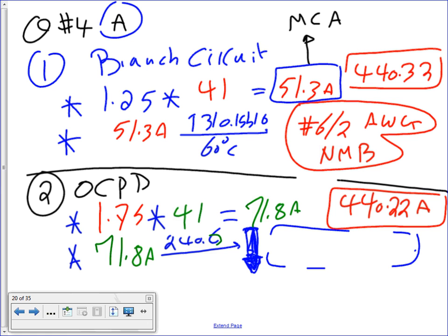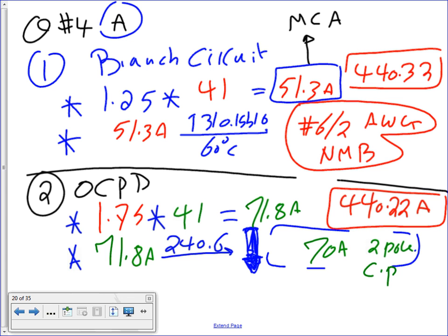240.6 here. If you take it to 240.6, same location that we've been. That will get you, when you go, you're going to go lower down to 70 amps. 70 amps, two-pole circuit breaker.